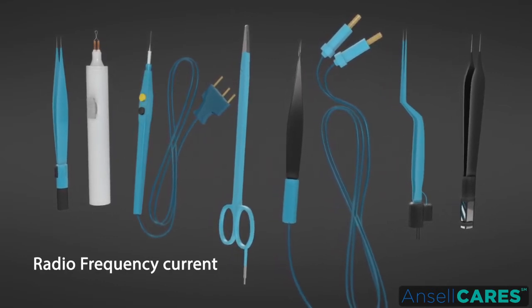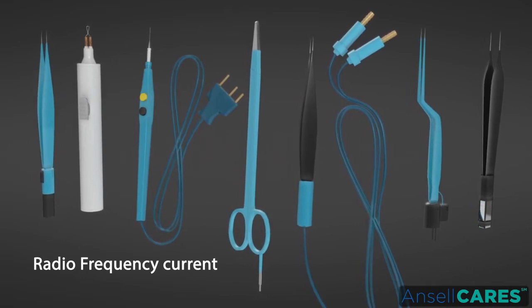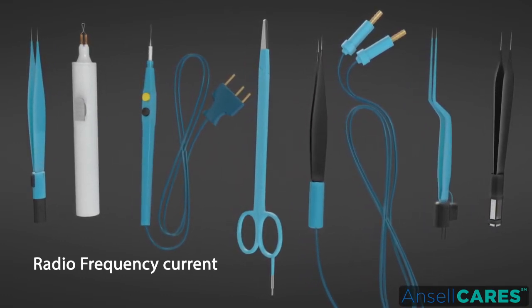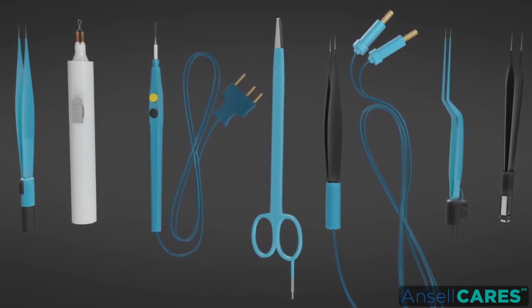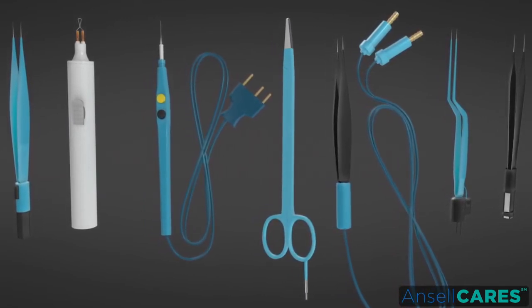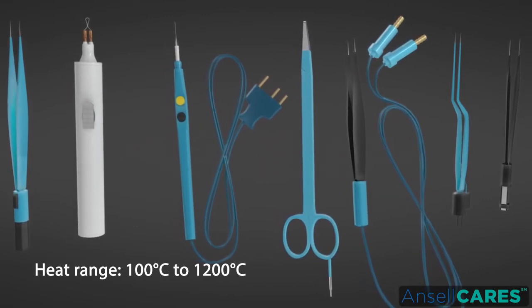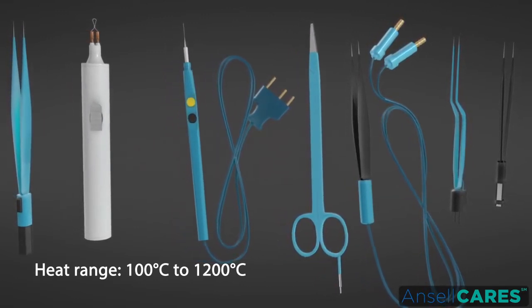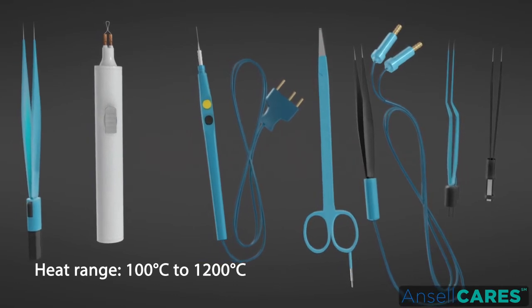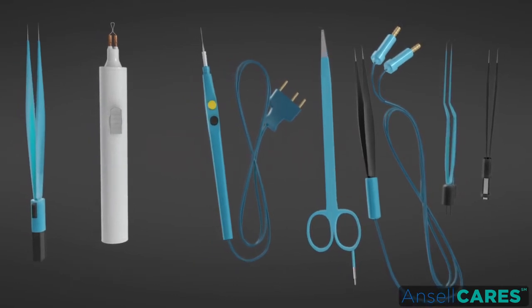There are various energy sources and methods employed with the use of electrosurgery. Radio frequency current is typically used by the surgeon to cut tissue, coagulate tissue to obtain hemostasis, or fulgurate tissue. An electrosurgery device can deliver heat at a range of 100 to 1,200 degrees Celsius, delivered by interchangeable tips such as loop, needle, and blade tips.